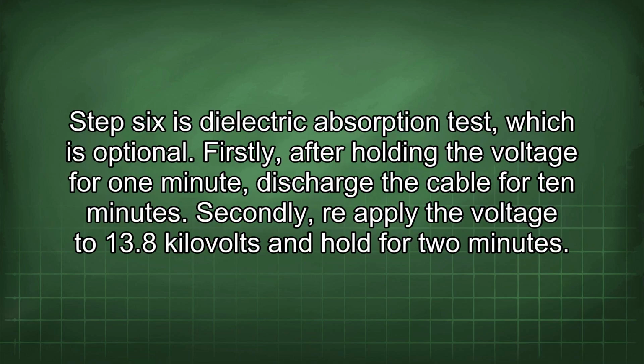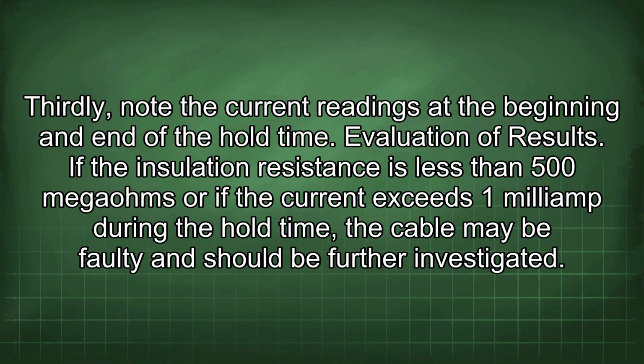Step 6 is dielectric absorption test, which is optional. Firstly, after holding the voltage for 1 minute, discharge the cable for 10 minutes. Secondly, reapply the voltage to 13.8 kV and hold for 2 minutes. Thirdly, note the current readings at the beginning and end of the hold time.